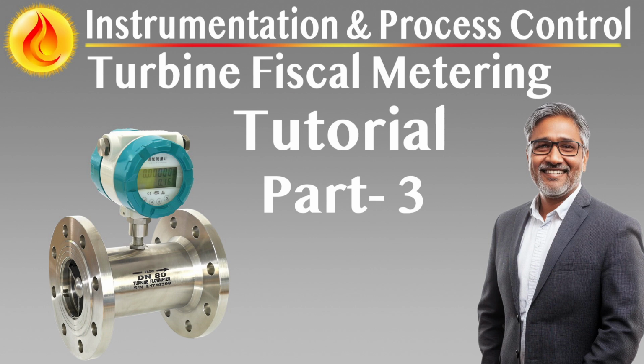Repeatability under stable conditions must be better than plus or minus 0.05% of mean pulse count. This performance must be verified at both minimum and maximum flow rates, as well as across several intermediate points throughout the operating range. Calibration checks must be conducted at both the manufacturer's facility and at site conditions to validate field performance against certified laboratory results.